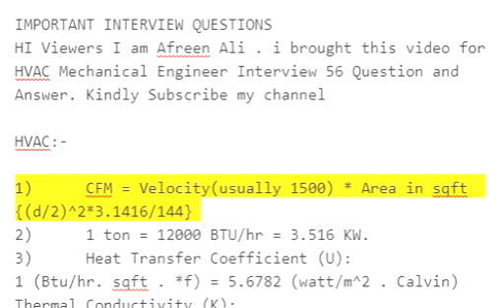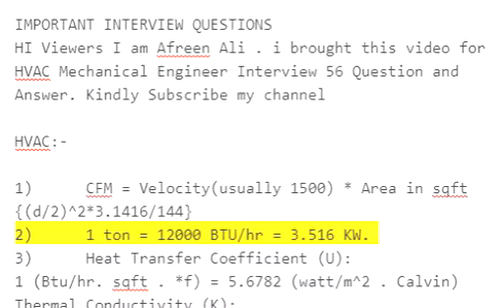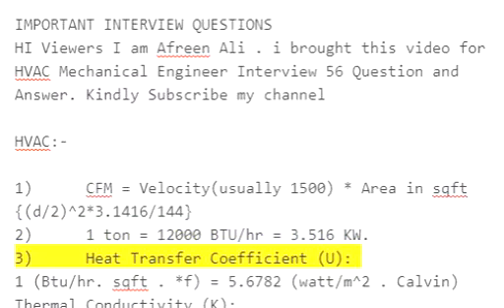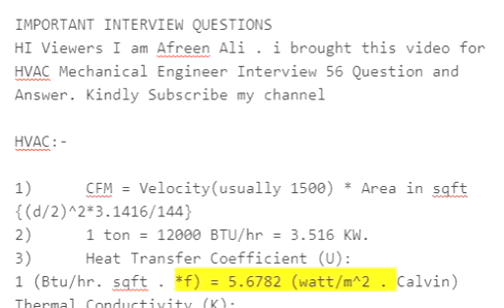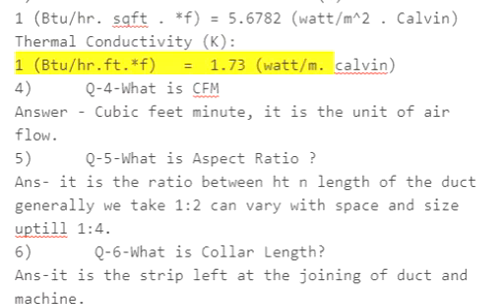Q2: 1 ton equals 12,000 BTU per hour equals 3.5 kW. Q3: Heat transfer coefficient — 1 BTU per hour per sq ft per °F equals 5.6782 W per m² Kelvin. Thermal conductivity k: 1 BTU per hr·ft·°F equals 1.7 W/m·Kelvin.